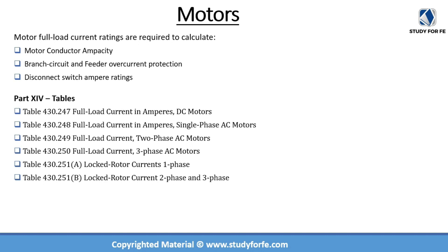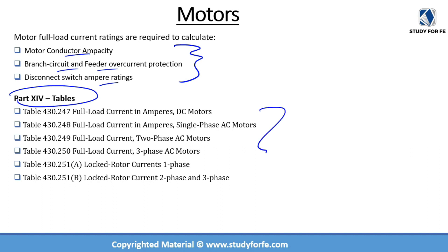The remaining seven parts are not directly related to motors but are indirectly related and still a worthwhile read. But the last part — Part XIV — which I didn't mention yet, is arguably one of the most important sections of Article 430 because it contains details regarding FLCs of the motors. Without FLCs, you cannot size a conductor, cannot size OCPDs for branch circuits, for feeder overcurrent protection, or for disconnect switches.